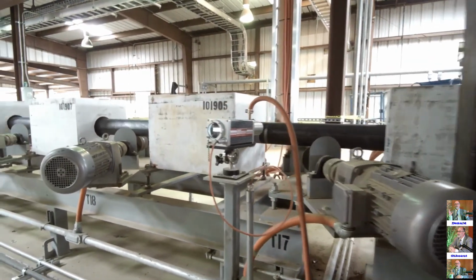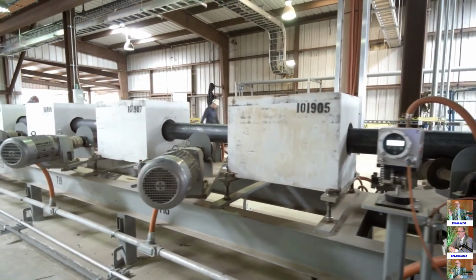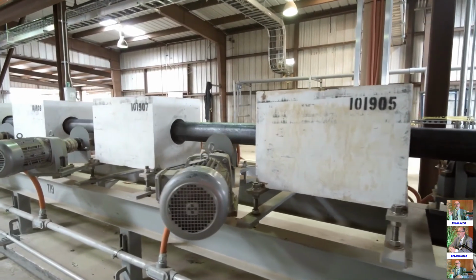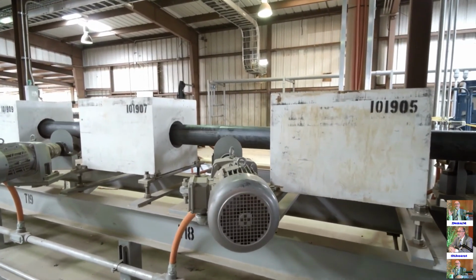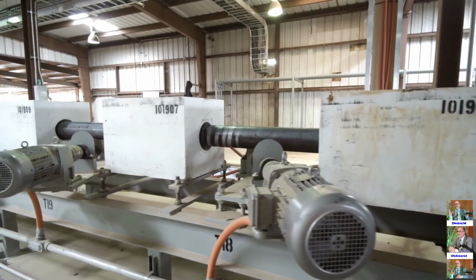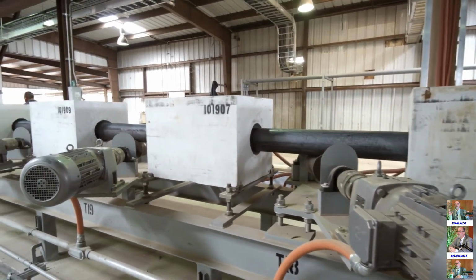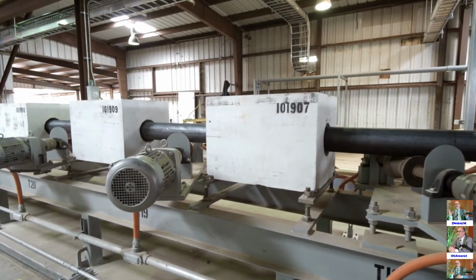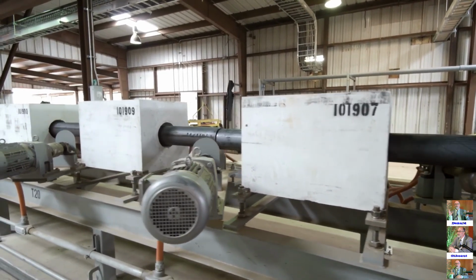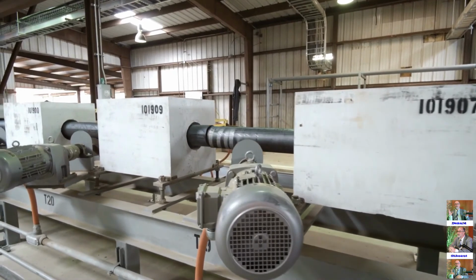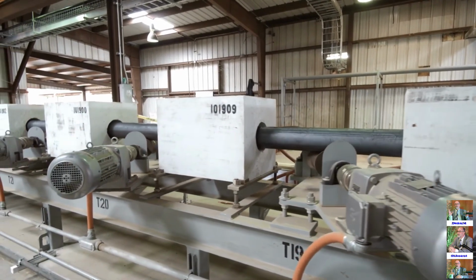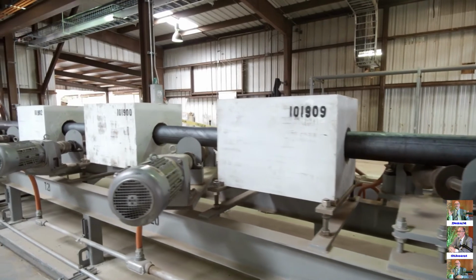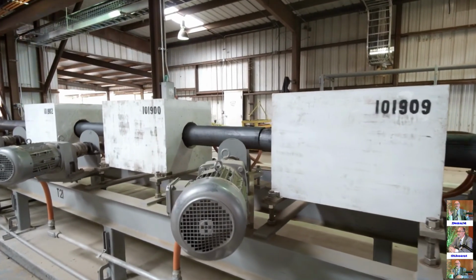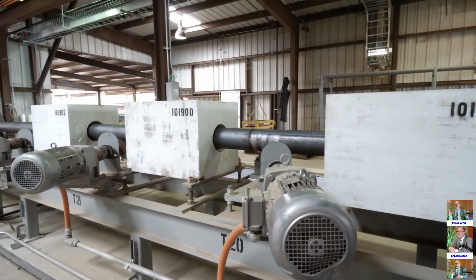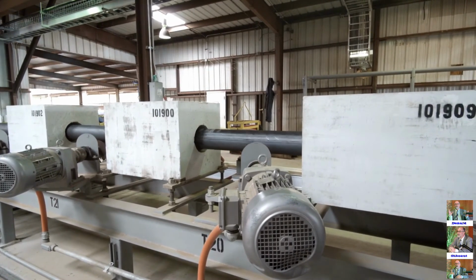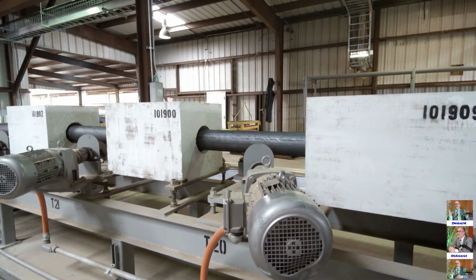Here's an infrared to the right that's reading out of the first power supply, and again we can feed forward to make adjustments to the second power supply in the condition that the ambient temperature has changed, or the resistivity of the base material has changed. That's a very nice versatile tool of induction, as you can adjust it and feed forward to the next power supply if you have multiple power supplies in the line. But you can see in the control, it's just very nicely controlled all the way through these induction coils.